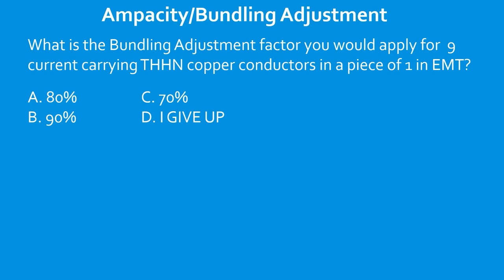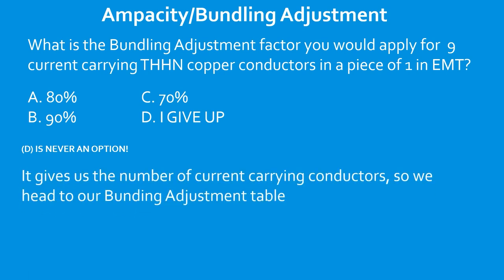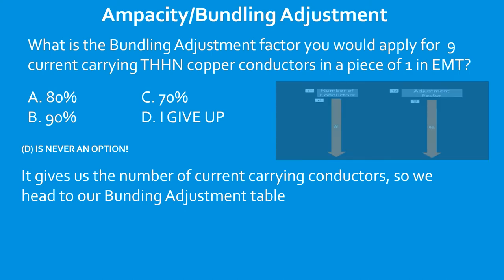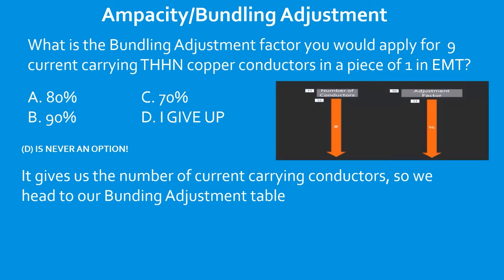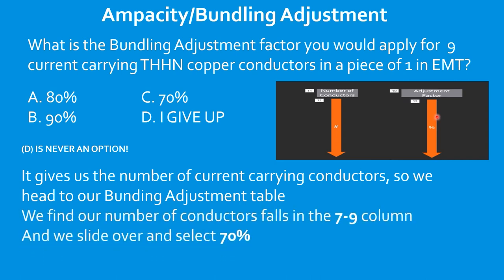Question: What is the bundling adjustment factor you would apply for nine current-carrying THHN copper conductors in a piece of one-inch EMT? Go to the bundling adjustment table, start on the left with the number of conductors. Nine falls in the seven-to-nine range. Come over and select the adjustment factor — 70%, which is 0.70. Select C.